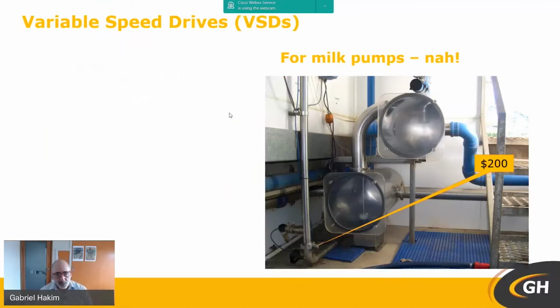Variable speed drives. Now, I see a lot of farmers wanting to put in VSDs on milk pumps, and we all know the reasons, but really, for $3,500, I can't see the benefit. A lot of these systems cost between 3 and 5 grand to install. I really can't see the benefit. The claims are about milk cooling improvements, yes, but really, if you fix the plate cooler, you shouldn't have a problem. If you do want to go down this track, why not consider a butterfly valve with a hole drilled into it as a flow restriction, as a way of restricting the flow? For $200, you can achieve the same outcome.